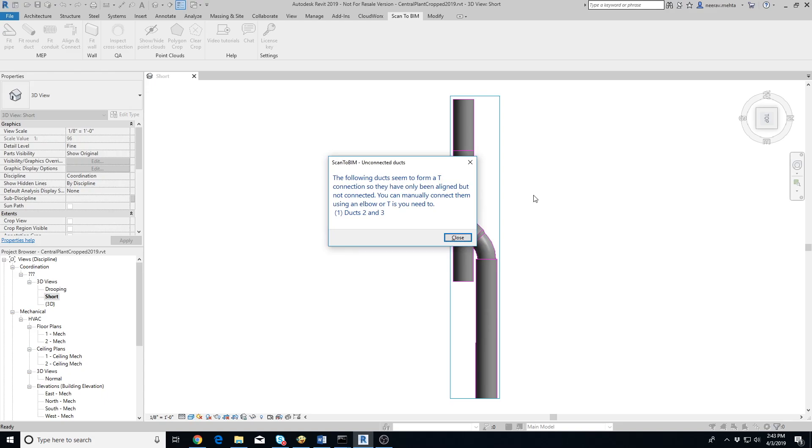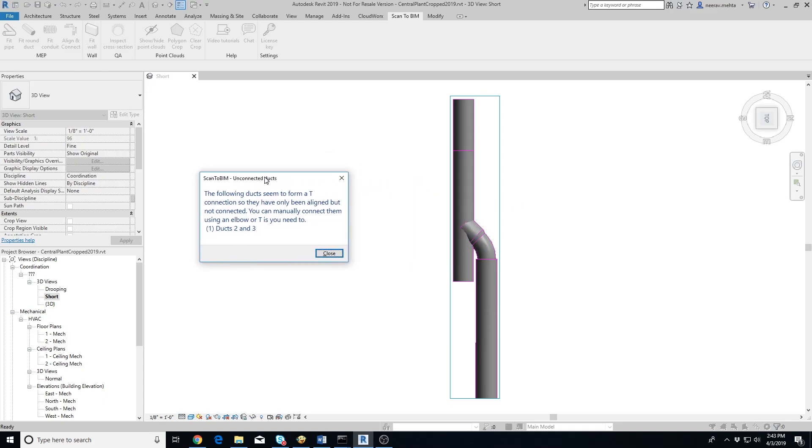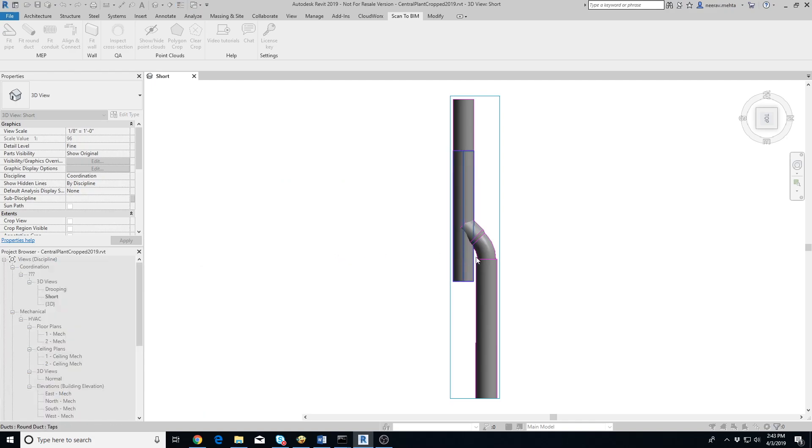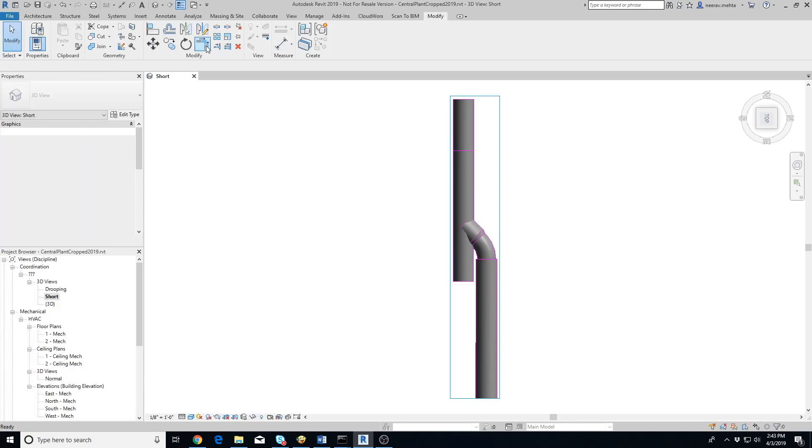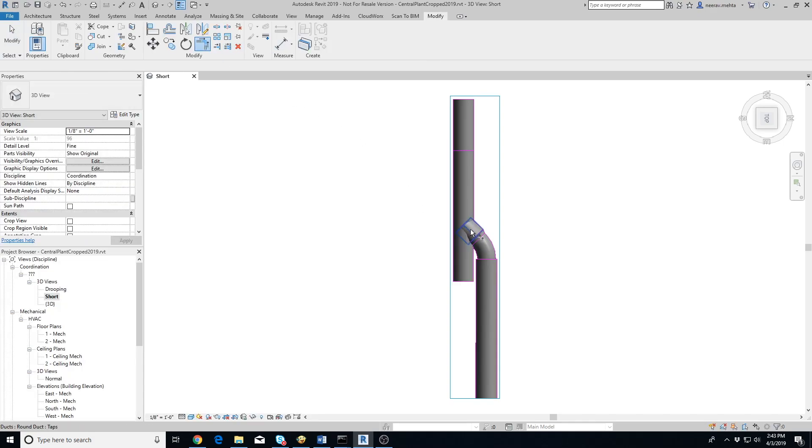Once it's done, it will show a pop-up listing the ducts which seem to be forming a T connection and not an elbow. You will need to add the T connections manually. In some cases, such as in the video, the add-in may misidentify a connection as T instead of an elbow. Just connect them using an elbow using Revit's trim slash extend to corner tool.